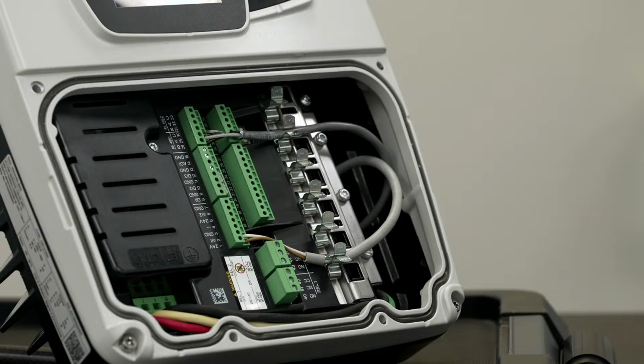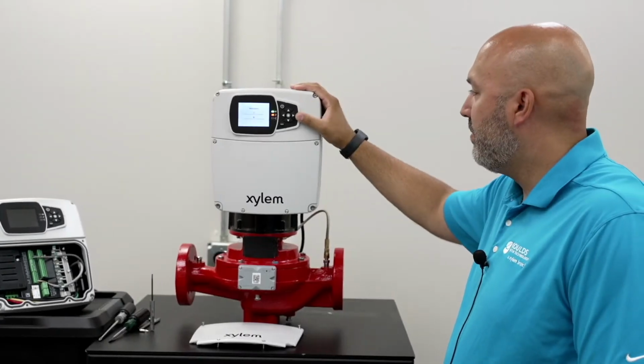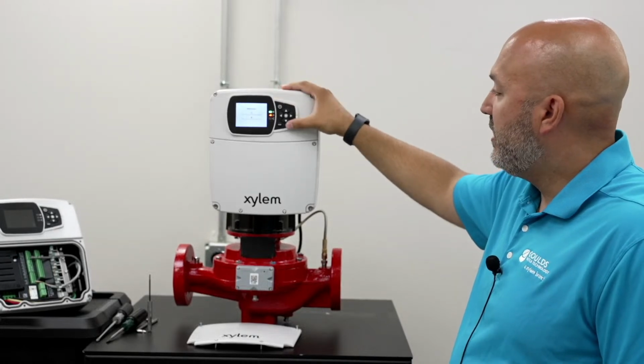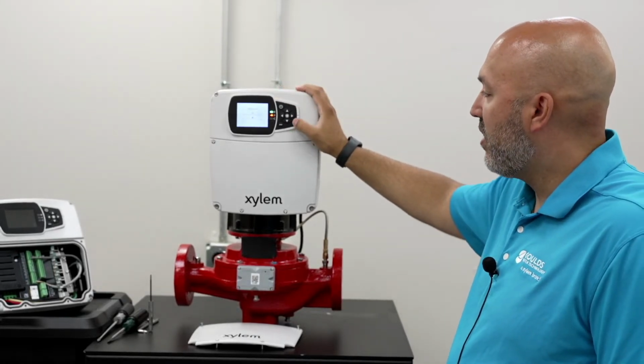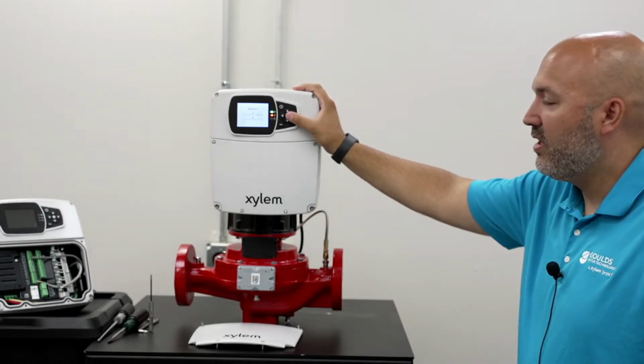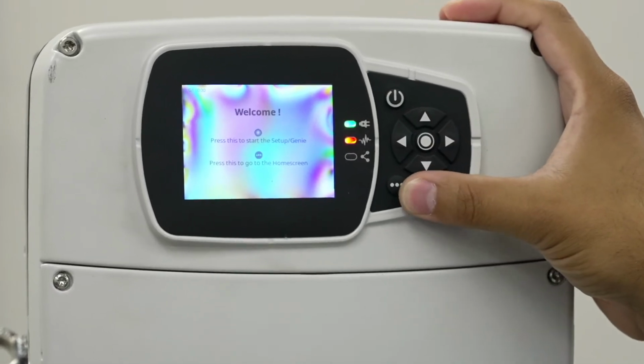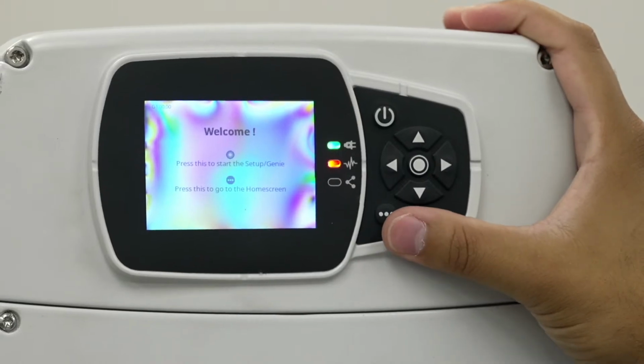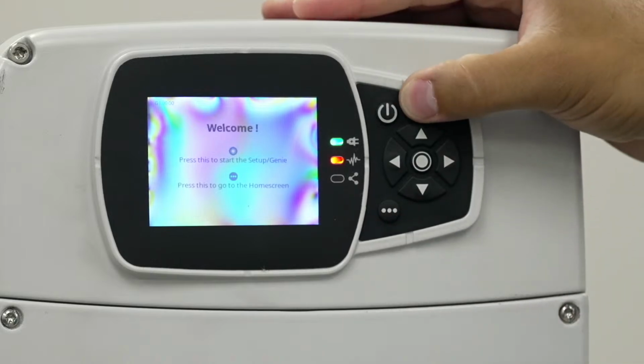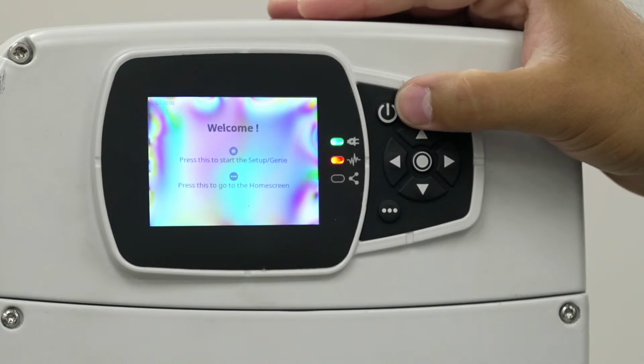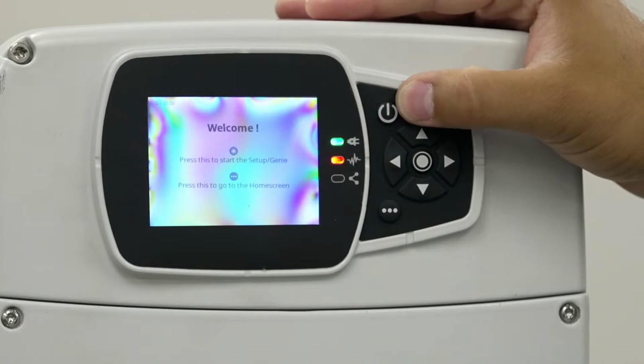But moving on to the HMI itself, we have this unit powered up. We just have the basic navigation buttons: up, down, left, right. The center button is your enter button. That's how you're going to confirm or select any parameters that you want. This is that multi-purpose or multi-function button I was discussing. That will get you into the menu group if you wanted to go beyond the 4 main home screens. Here is an on-off button. Although it has that power symbol, it is not actually going to cycle power or turn off power going to the unit. This is simply going to start or stop operation of the pump and motor. So that is a start and stop, not a power.